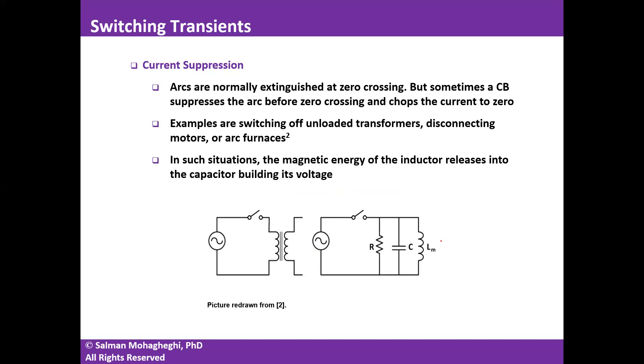We often open circuit breakers at zero crossing of current in high-voltage applications, but in smaller-scale applications we don't have the means to monitor the current waveform. For example, when you turn on or off an appliance at home, you don't know when the zero crossing occurs. When you open the circuit breaker, it is very likely the current is not zero — you're chopping that current to zero. We call that current suppression.